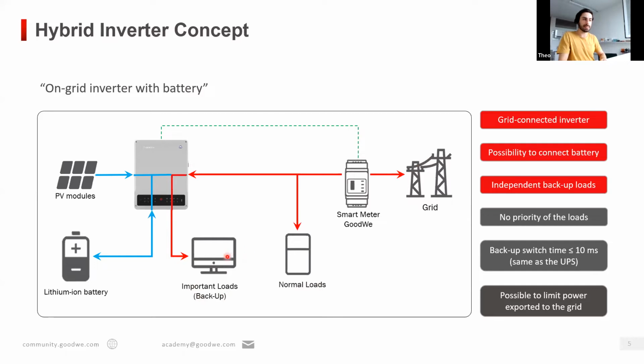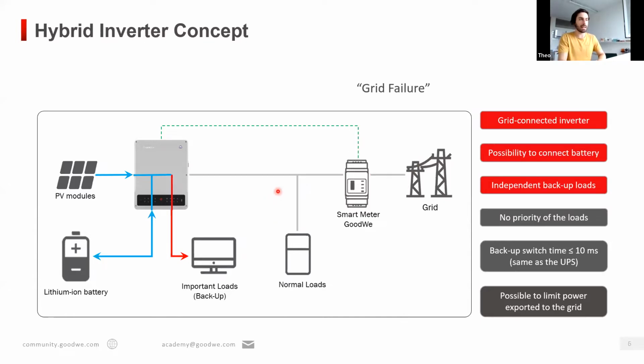Important to mention is that when the grid is active, there's no difference between those two loads. They are powered equally from the PV modules, the battery, and from the grid. So there's really no difference between those. However, the difference is when there is a grid outage. If you have a grid outage, this side here will disconnect because of regulations and for safety, the inverter is then not allowed to feed out any power on the same line that's connected to the grid. Instead, you have the backup power here, which will keep on working.